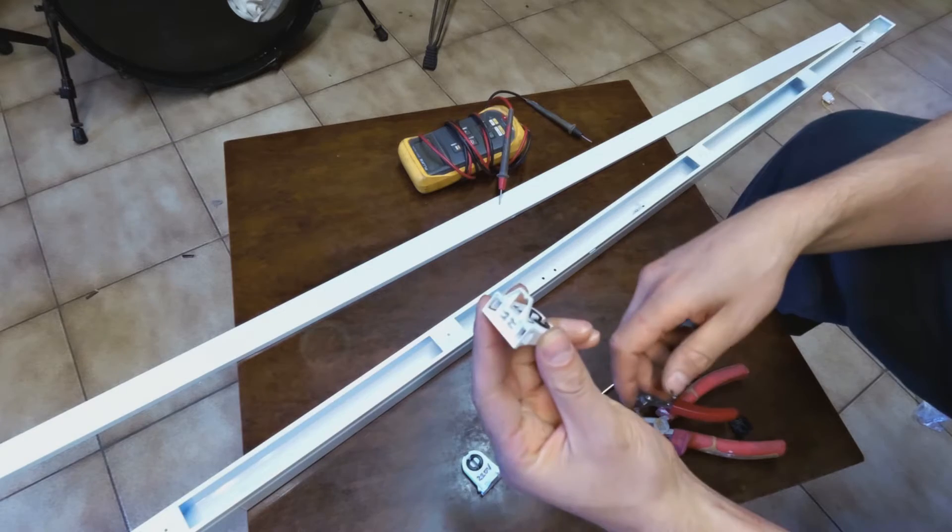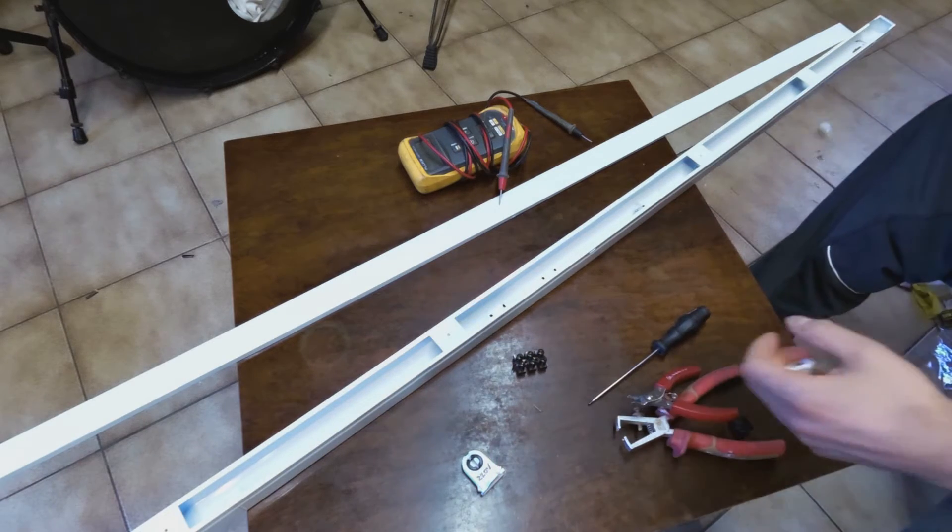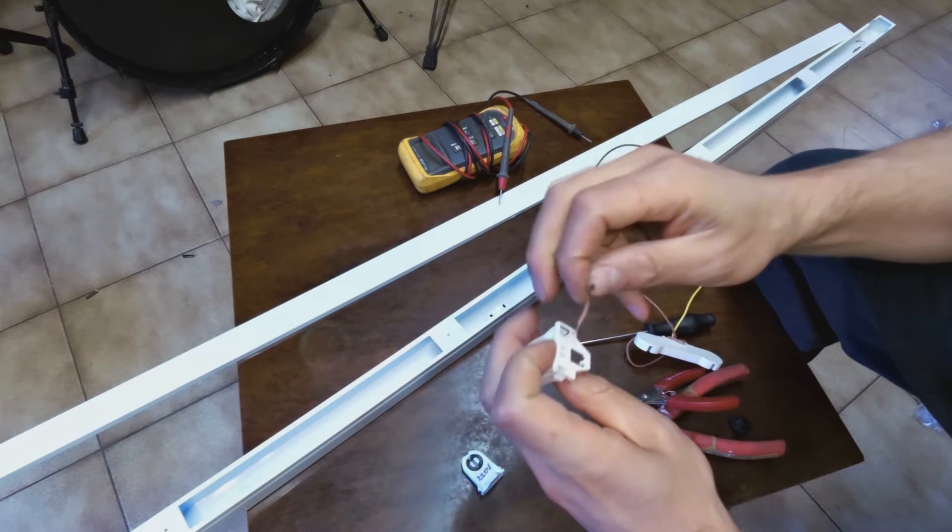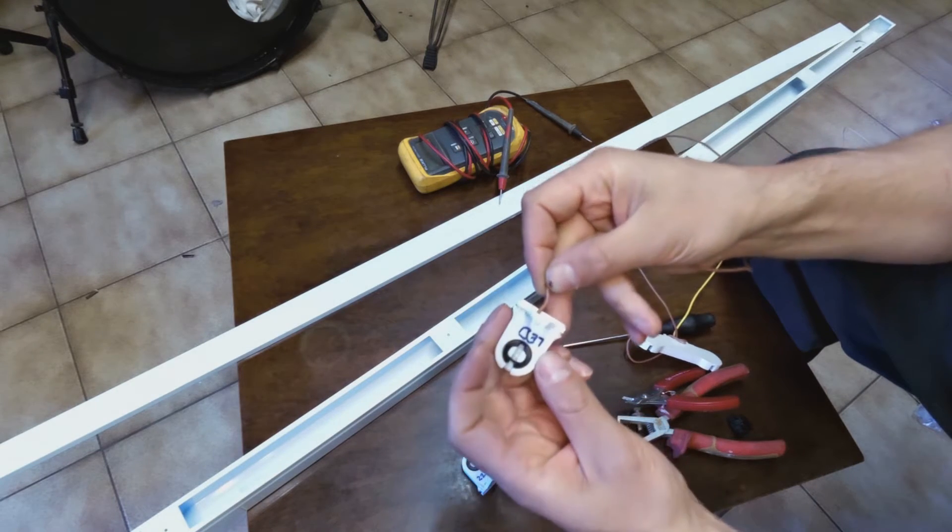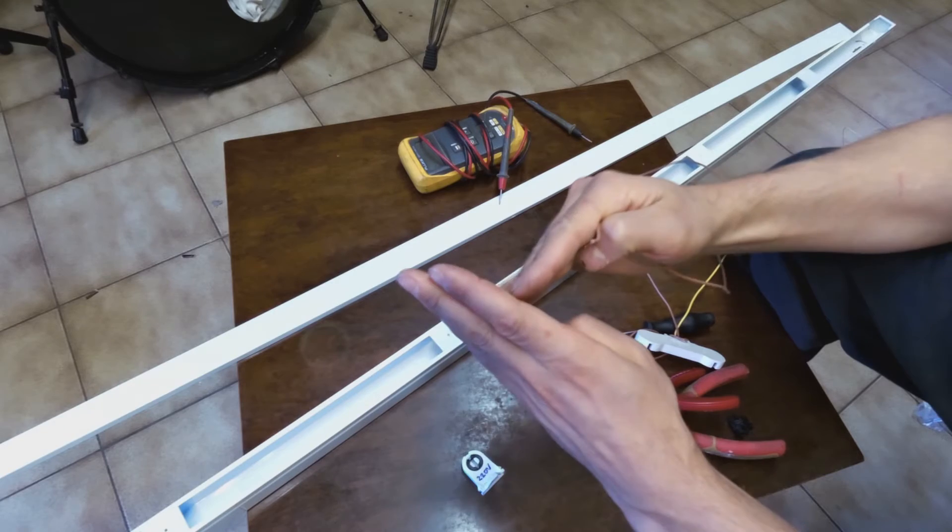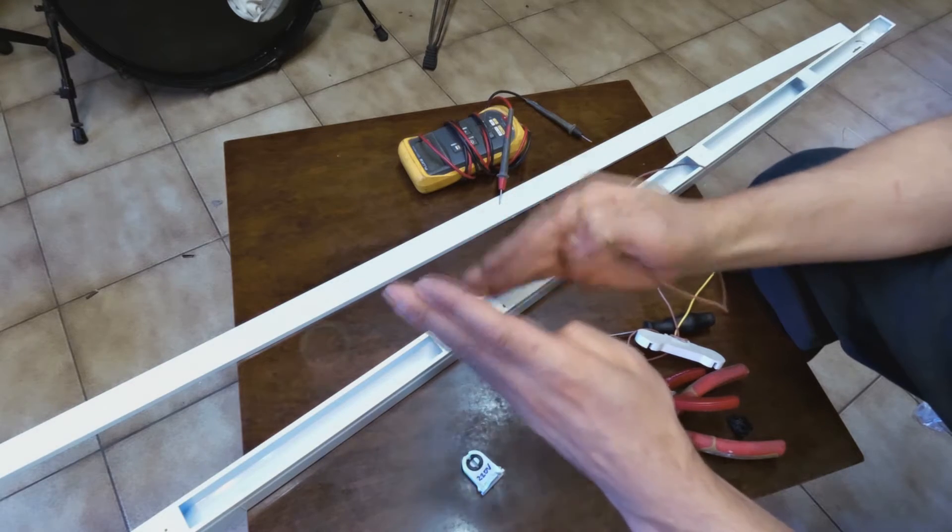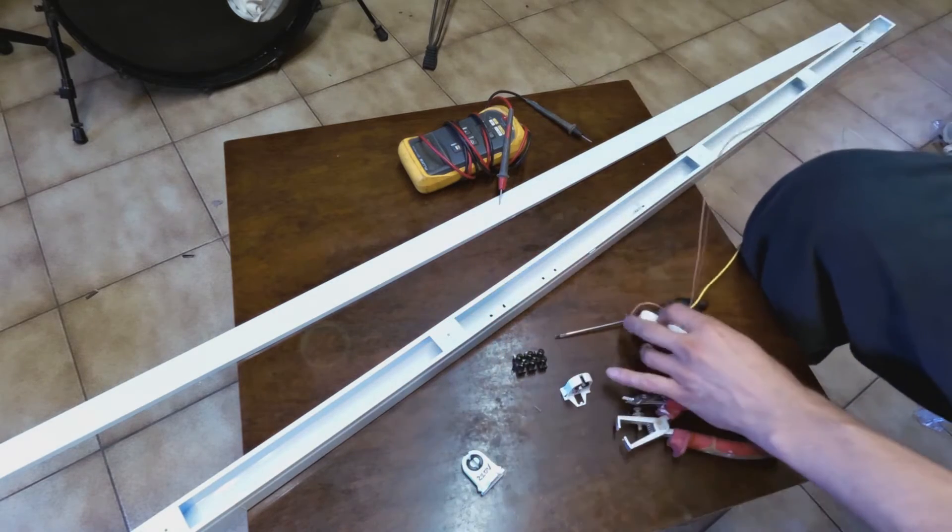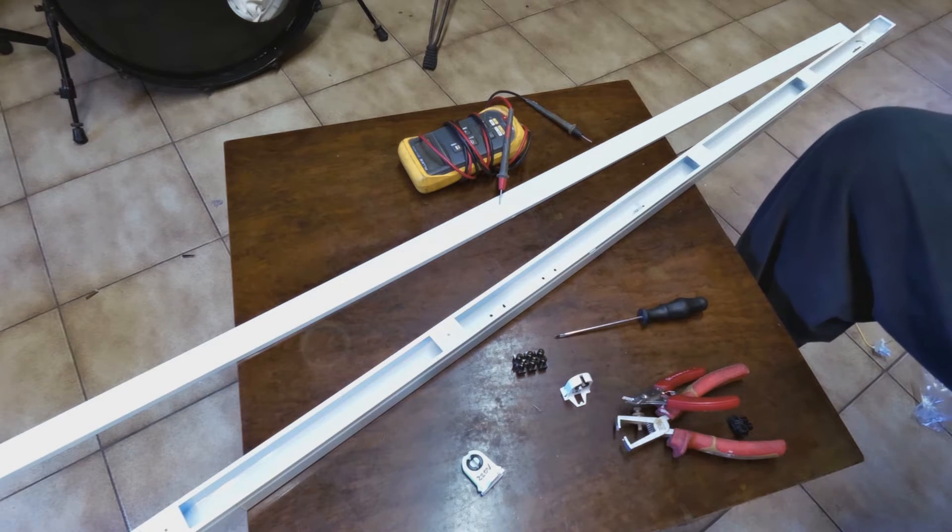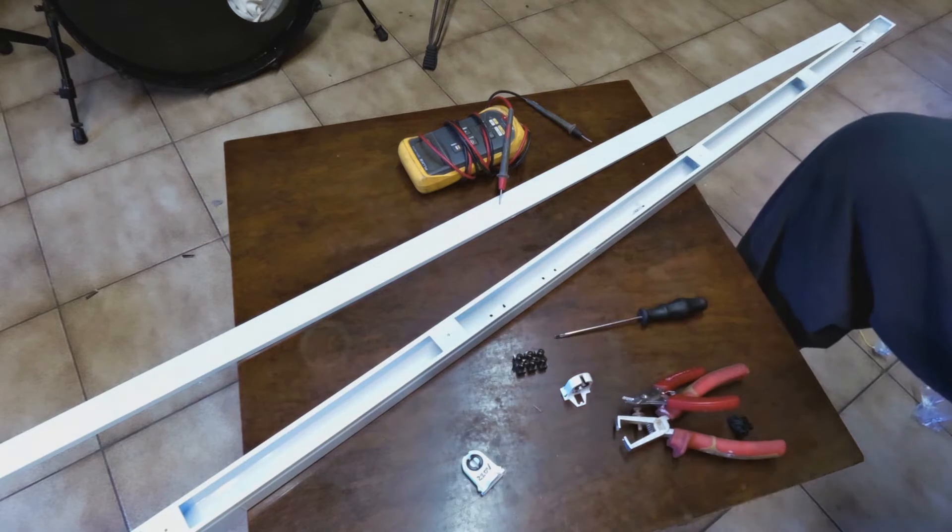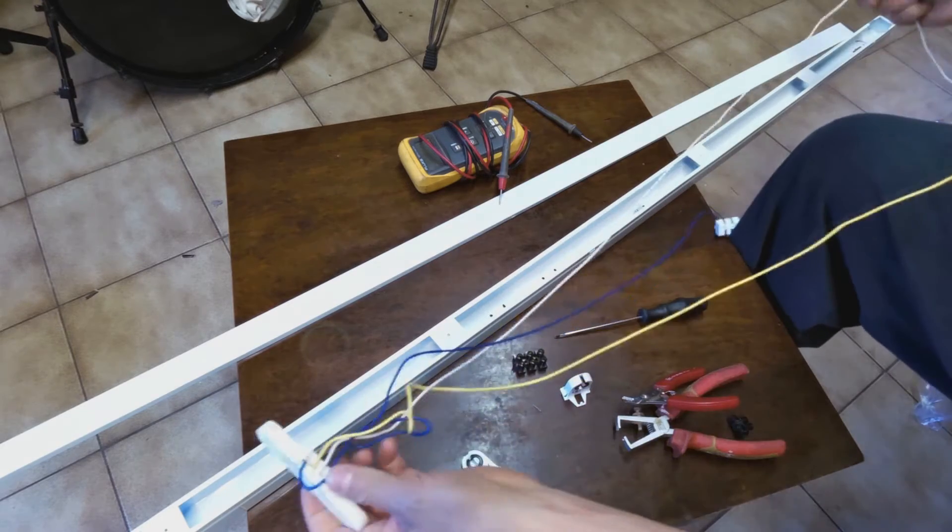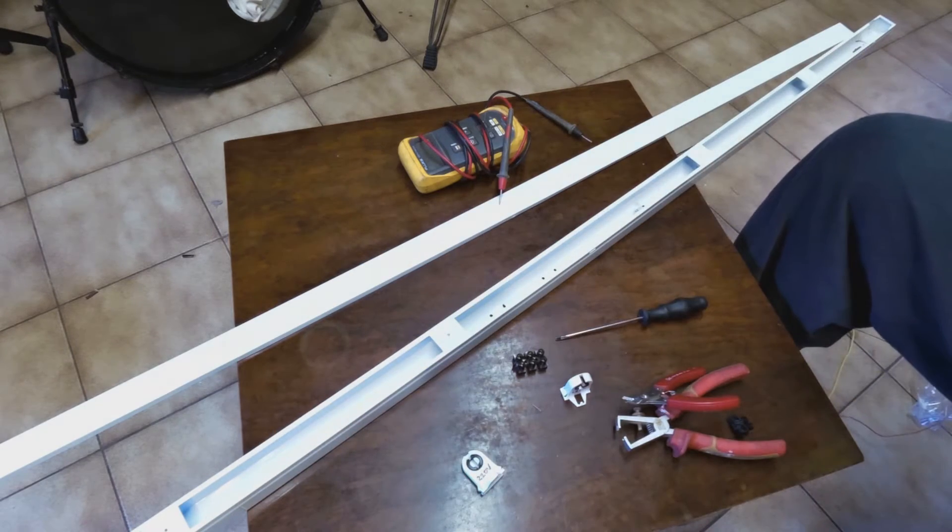Because of these fittings you need to use a solid wire. For example, the wire that I just removed, if you look at it it's solid. The reason why we use it is because when you put it in the fitting it just slots in, and when you pull it back it actually gets wedged by a flap of the copper. So I recommend using solid cable and not stranded. So what I've got is some cable here. You can either use the one that you just stripped, which maybe is a good idea. I'll probably just use these ones that I've just removed.